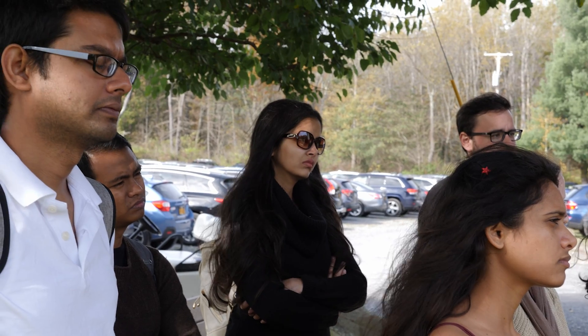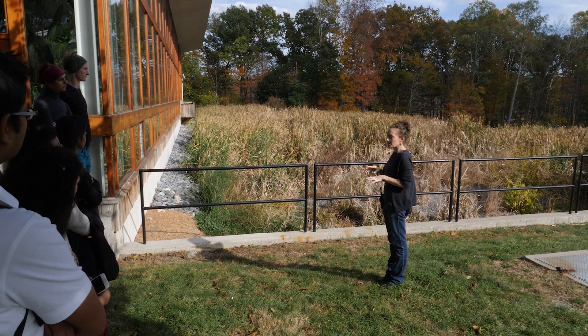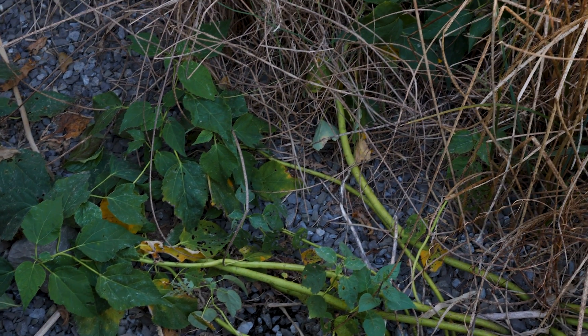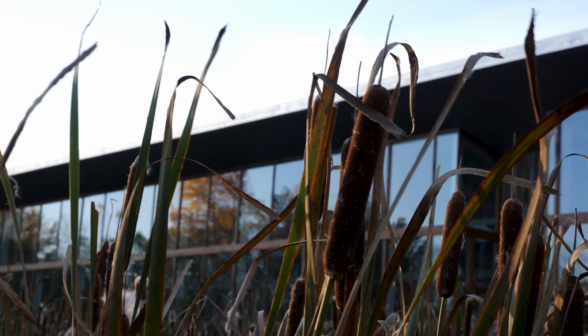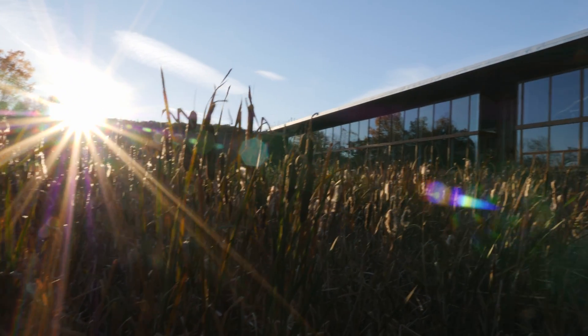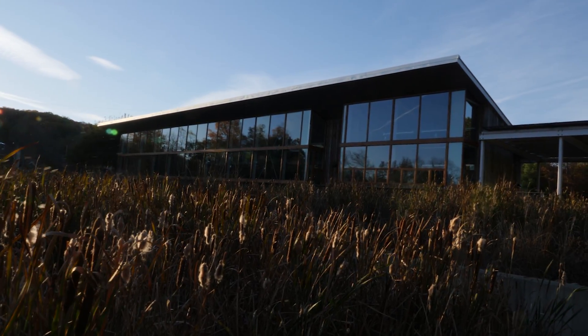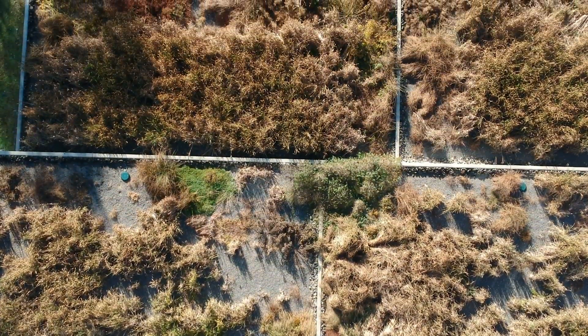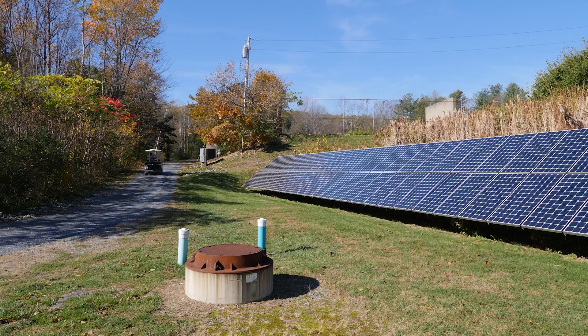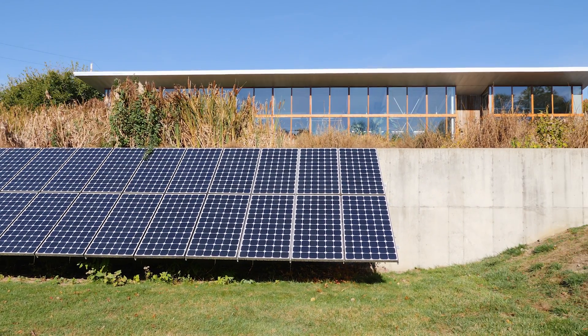At this point the water is not going into the ground — you have it all being treated here. The relationships that the plants have with the microbiology, the root systems, and the gravel provide surface space for all the different organisms and the diversity of what's in here. Out here are all the native plants — cattails, bulrush, swamp aster, and different wetland flowers. That is gravity fed into the second two cells; once it reaches a certain level and has been in here long enough, it goes to the next two cells, and a solar-powered collection at the bottom pumps it up into the lagoon.